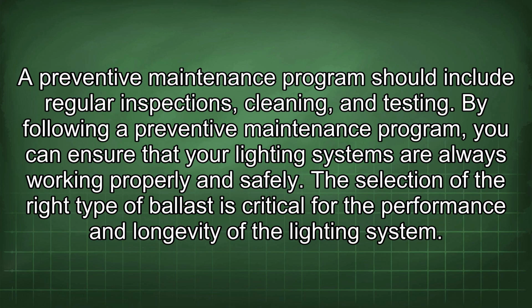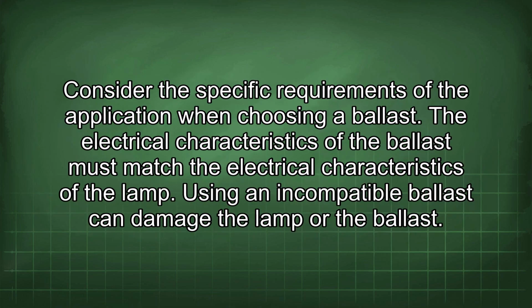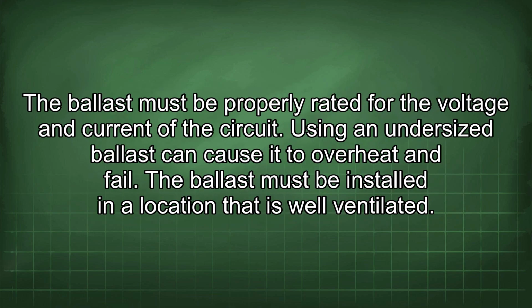The selection of the right type of ballast is critical for the performance and longevity of the lighting system. Consider the specific requirements of the application when choosing a ballast. The electrical characteristics of the ballast must match the electrical characteristics of the lamp. Using an incompatible ballast can damage the lamp or the ballast. The ballast must be properly rated for the voltage and current of the circuit. Using an undersized ballast can cause it to overheat and fail.